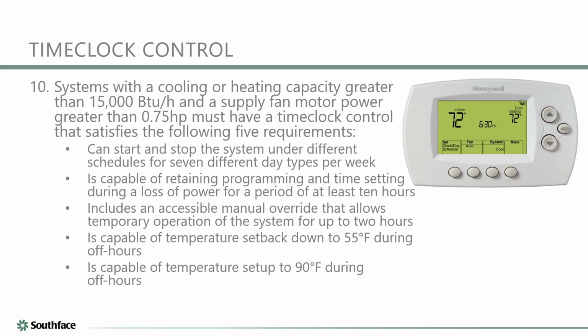You also have battery backup, basically for the timing, so that if you do lose power, you'd be able to retain those settings, because we know that our occupants, our building managers and such tend not to reset those controls either after a loss of power or even after a time change sometimes.